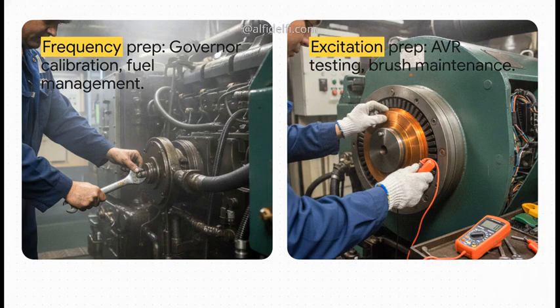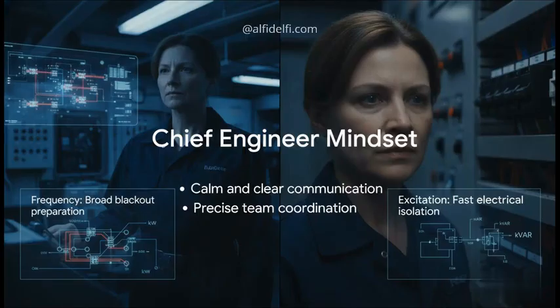You've got to enforce strict AVR testing protocols, meticulous maintenance of brushes and slip rings, and regular calibration of your protective relays. Under the SOLAS and ISM codes, real leadership requires adopting the exact right mindset for the specific fault you're facing. A frequency issue requires broad, system-wide blackout preparation. An excitation issue, on the other hand, demands fast, precise electrical isolation. In both scenarios, calm communication and coordinated team training, which means running separate, distinct drills for both faults, are your ultimate tools. That's how you turn a potential disaster into demonstrated competence.